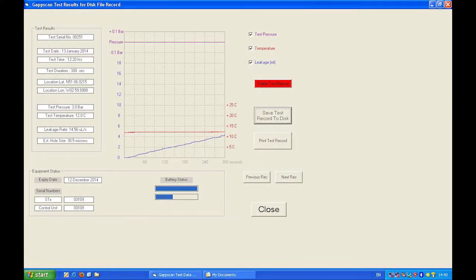From the tests we conducted today, you can see that at pressures of 3 and 4.9 bar, the estimated hole sizes are larger than 20 microns. We investigated further by running a lower pressure test at 1.5 bar and the estimated hole size is 17.9 microns. The defects are thus multiple and within acceptable levels at the lower pressure.